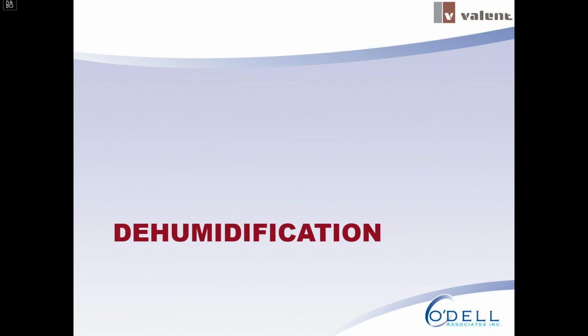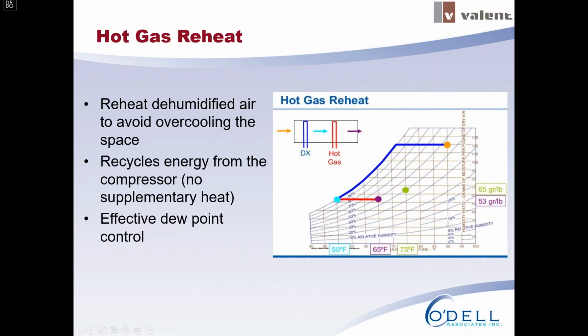Excellent. So Nathan touched on hot gas reheat, and I alluded to it in my previous slides, but I think now is a good time for us to dive right back in and talk about what that is exactly. Hot gas reheat is essentially a way to take the cold saturated air that comes off the DX coil and reheat it back up to a more comfortable, room-neutral temperature. In this psychrometric chart, we're showing that we dehumidify down to 50 degrees, for example, and then we're reheating back to 65. Essentially, we're taking recycled energy from the compressor, normally hot gas that would go to the condenser coil and be exhausted as waste heat. We're going to reclaim some of that heat and use it to reheat our airstream.